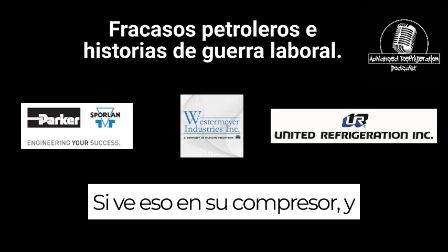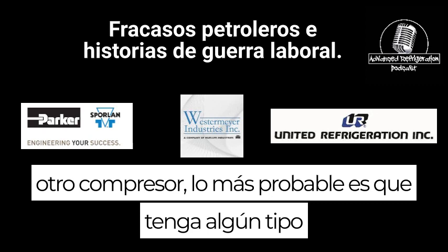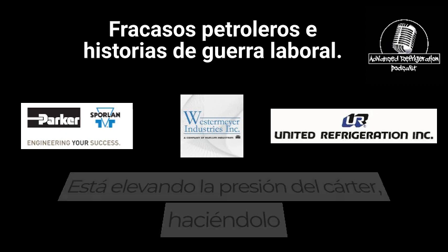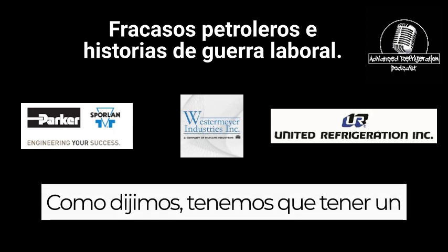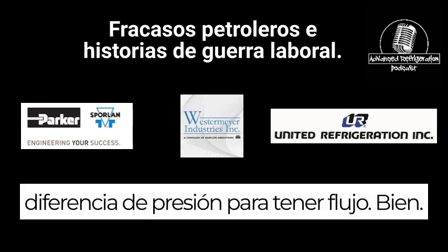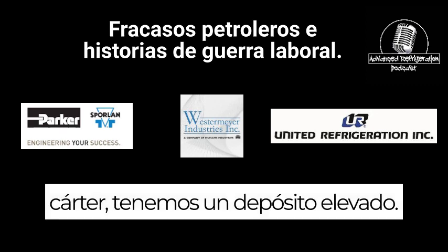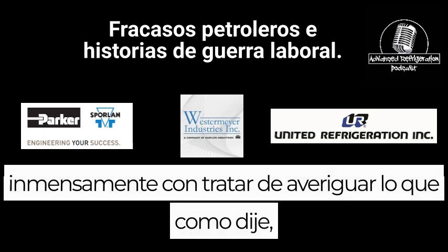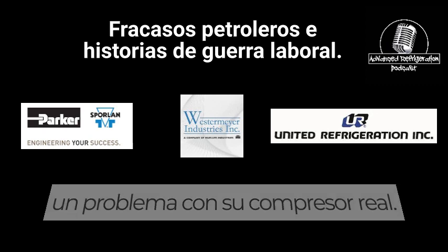If you see that in your compressor and there's no equalization line between the compressor and the other compressor, chances are you have some sort of blowback that's preventing that oil from actually going into the crankcase. It's elevating the crankcase pressure, making it higher than the reservoir pressure. Like we said, we have to have a difference in pressure in order to have flow, right? So if we have an elevated crankcase and an elevated reservoir, there's no flow. So look for that misting. That will help you out immensely with trying to figure out what it might be. Like I said, it might not be an actual oil float or oil pot issue. It might be that you have an issue with your actual compressor.